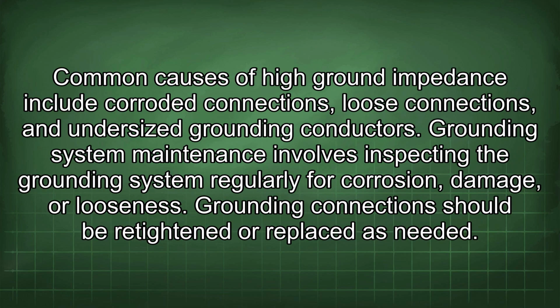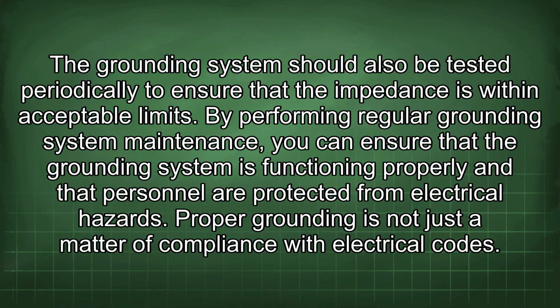Common causes of high ground impedance include corroded connections, loose connections, and undersized grounding conductors. Grounding system maintenance involves inspecting the grounding system regularly for corrosion, damage, or looseness. Grounding connections should be retightened or replaced as needed. The grounding system should also be tested periodically to ensure that the impedance is within acceptable limits. By performing regular grounding system maintenance, you can ensure that the grounding system is functioning properly and that personnel are protected from electrical hazards.